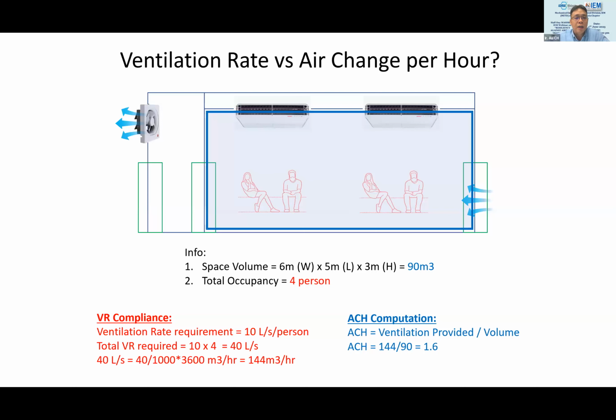Okay, before I go further, I realize there are a lot of questions asking what actually is 10 liters per second and what is ACH. How are they related? They are actually related. ACH is air change per hour, meaning the amount of air that is changed in 1 hour, how many times the volume of the space is replaced in 1 hour. That's what we mean by air change per hour of outdoor air. Liters per second means the number of people in the room multiplied by the required liters per second, which is the flow rate at which you introduce air into the space.